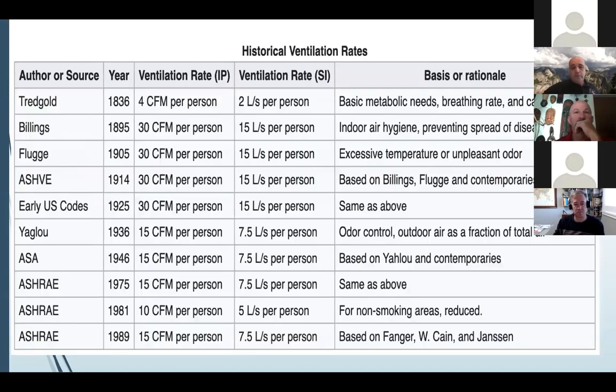Here's the history of ventilation rates throughout the years. In the late 1800s it was common to have 30 CFM of fresh air per person, and that ran through the mid-1900s as the standard to keep people healthy and prevent disease spread. In the mid-30s it changed to 15 CFM, which ran for quite some time. Then, during the energy crisis, it was changed to 10 CFM to save energy. But then we had a rash of sick building syndrome, so it was increased back to 15 CFM per person in the late 80s, and today it's still about 15 CFM per person—today's standard, set by ASHRAE.